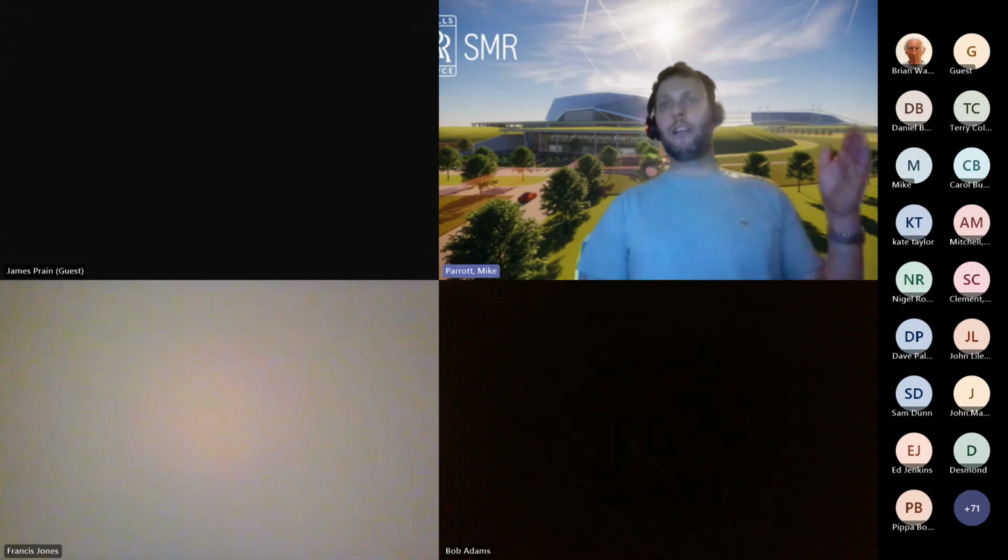As an example, as a verification and validation activity on a valve, we're designing an ASME plant. We're designing it to the ASME design code, and as part of that design code, we have to do qualification testing of certain valves that need to either safely support safe shutdown of the power station or safe operation of the shutdown. One of those valves, as an example, is the main steam isolation valve, and we have to therefore put it through a qualification test, and that qualification test is a shaker test, full flow, etc.